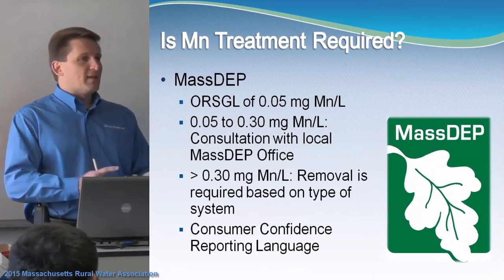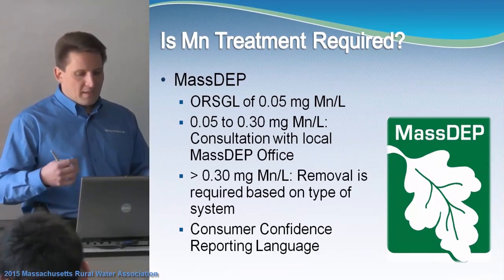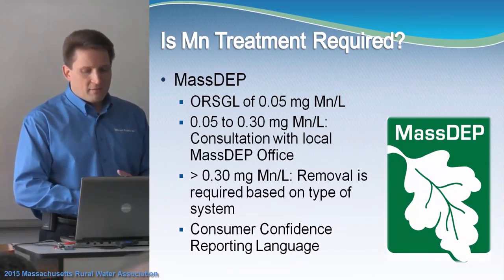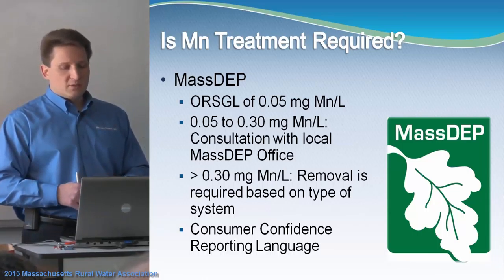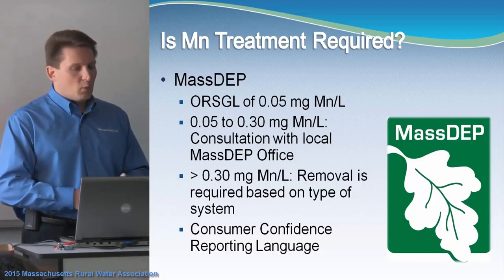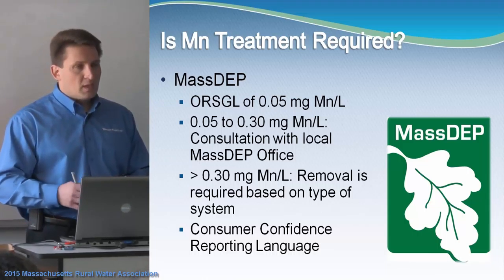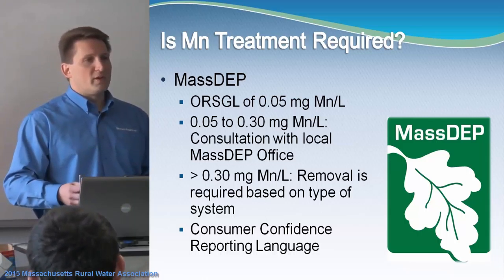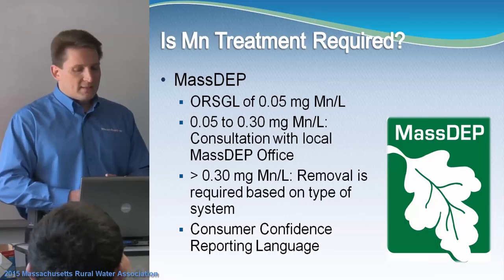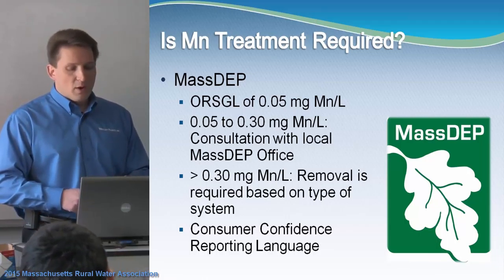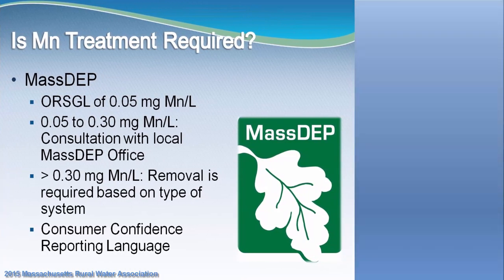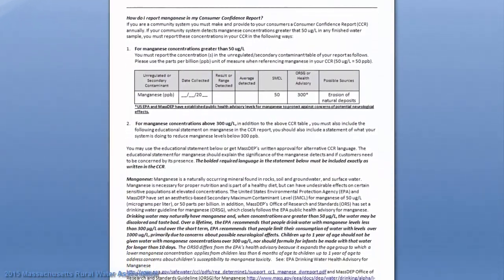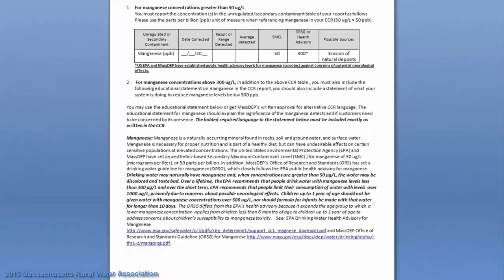From the DEP's perspective, they have the Office of Research Standards guidelines with a level of 0.05 milligrams per liter. If you have manganese in your treated water between 0.05 and 0.3, you'll have to consult with your local MassDEP office. If it's over 0.3, you will probably have to remove it, depending on the type of system. The DEP has also been asking utilities to include language about manganese and its concerns in the Consumer Confidence Report.